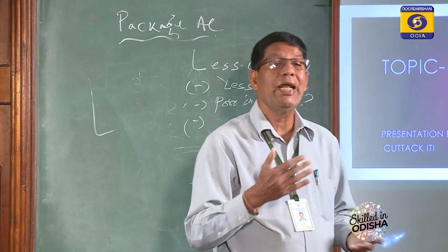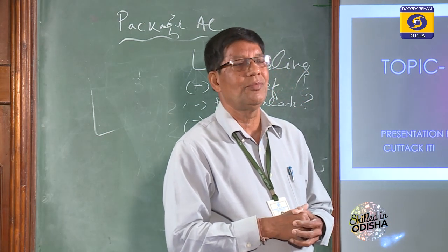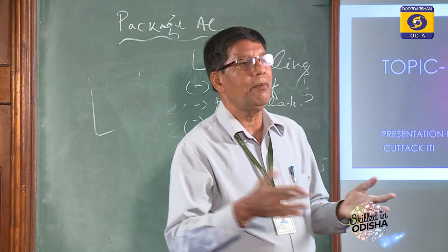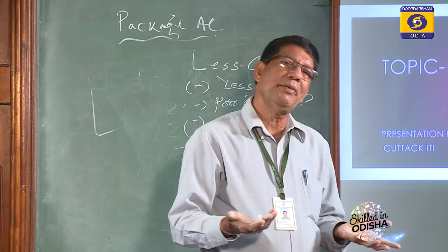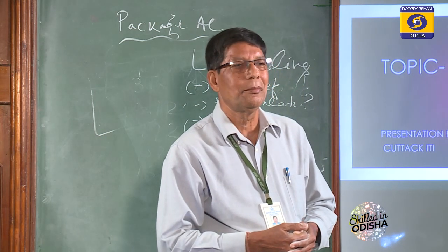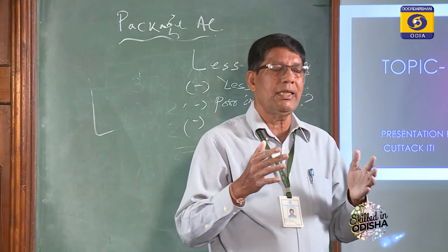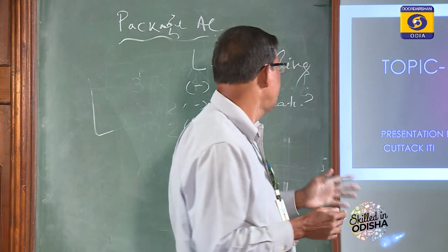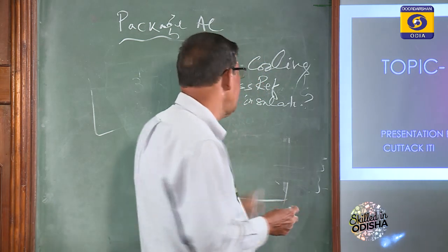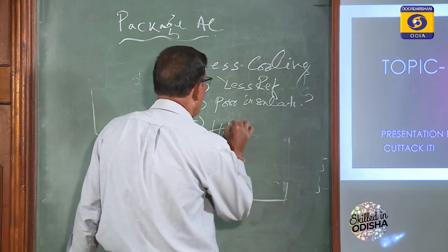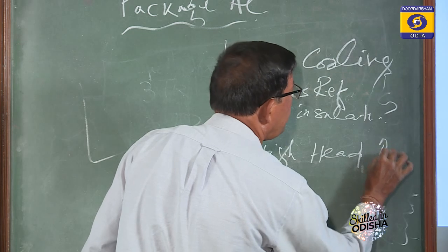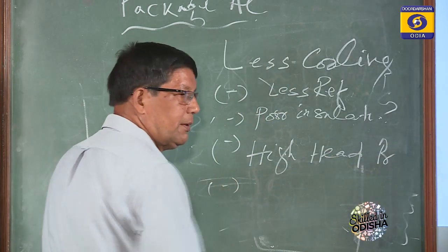Another thing is a dirty condenser. The motor is running, but at low speed. Improper water pressure, dirty condenser. So these are the causes of high head pressure. This is known as high head pressure.